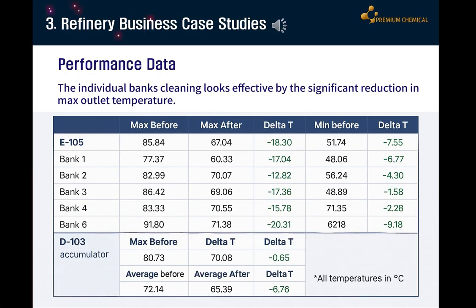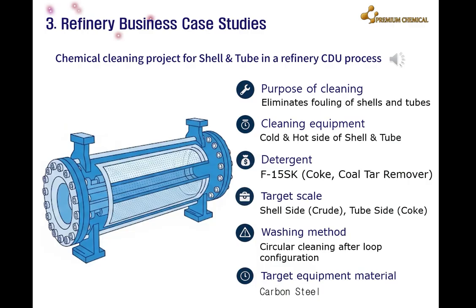The temperature of the D103 accumulator also decreased by approximately 10 degrees Celsius, indicating that the cleaning had a positive impact on surrounding equipment. The following illustrates a case study of chemical cleaning for a shell and tube heat exchanger in a refinery's CDU process.